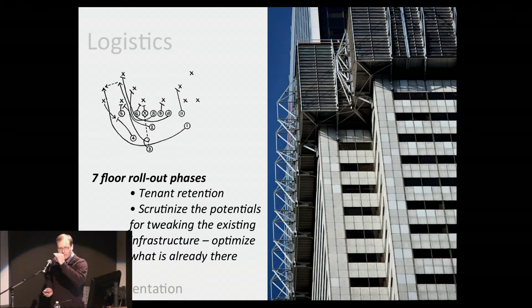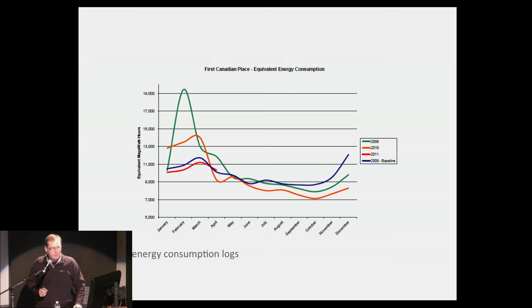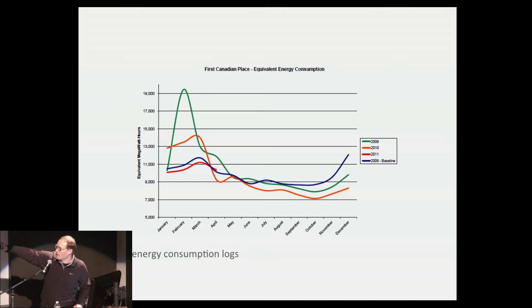Here we're tracking some of the energy consumption. One of the challenges is that as these systems are put in place, nobody really knows how to operate or balance them yet. It usually takes several months or sometimes years. The blue line is our baseline curve moving from summer to winter. In 2009, all the new chillers are thrown on and they're not quite balanced, so there's a spike in energy consumption. But we're getting down now — we have data beyond this — and in 2011 we're starting to creep just below our baseline.